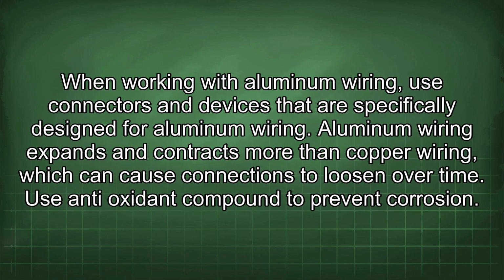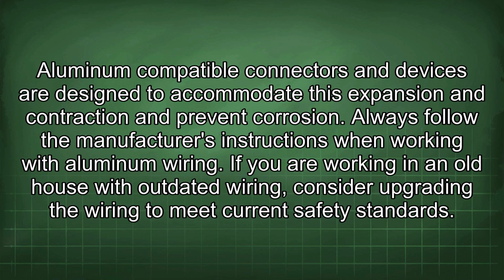When working with aluminum wiring, use connectors and devices that are specifically designed for aluminum wiring. Aluminum wiring expands and contracts more than copper wiring, which can cause connections to loosen over time. Use antioxidant compound to prevent corrosion. Aluminum-compatible connectors and devices are designed to accommodate this expansion and contraction and prevent corrosion. Always follow the manufacturer's instructions when working with aluminum wiring.